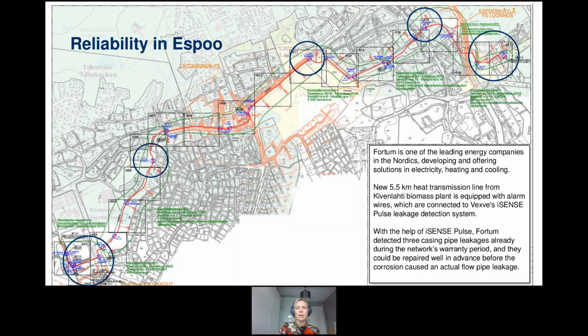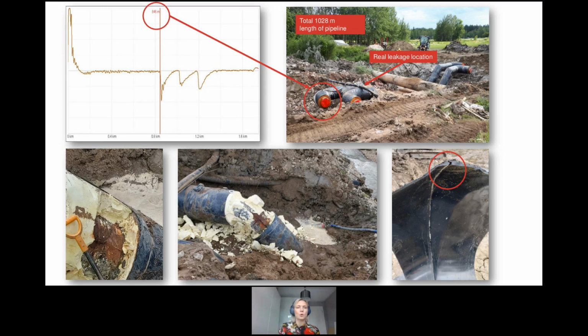And I will show you in the next slide a couple of photos from the sites and how the case went forward. First of all, we noticed that since the beginning of the pipeline, there has been some problem at 847 meters from the measuring point. After that, we went on site, and with a portable TDR measurement, we made a more precise location of the leakage at 850 meters, which is very close to the point that the system was originally showing.